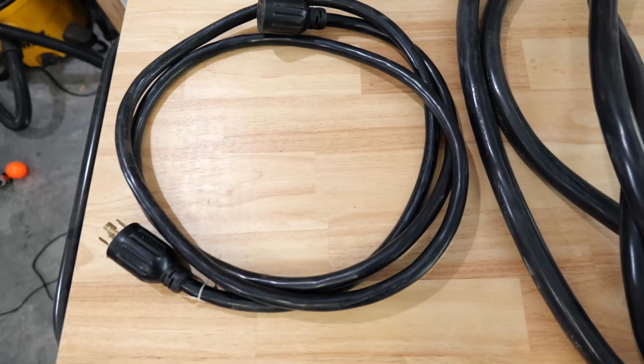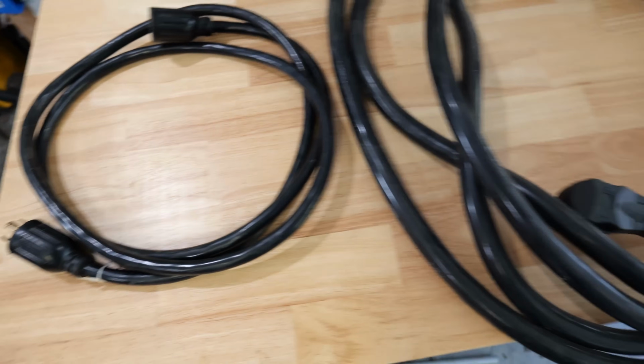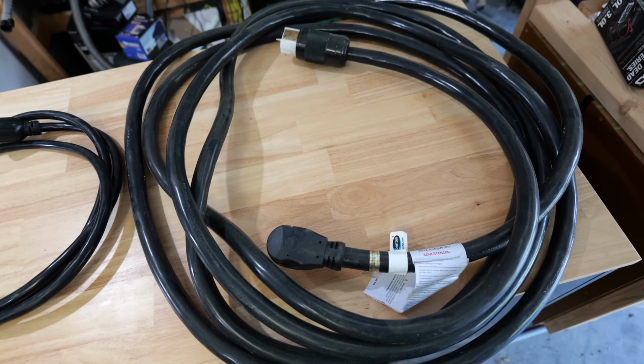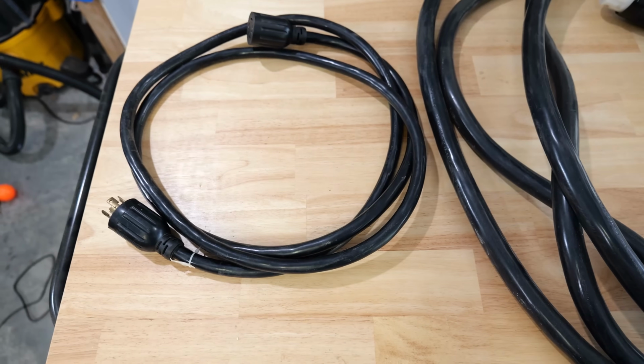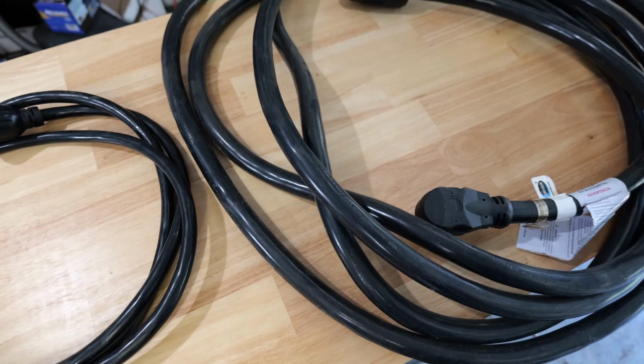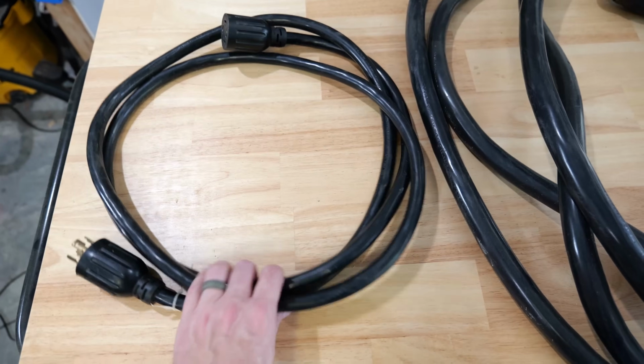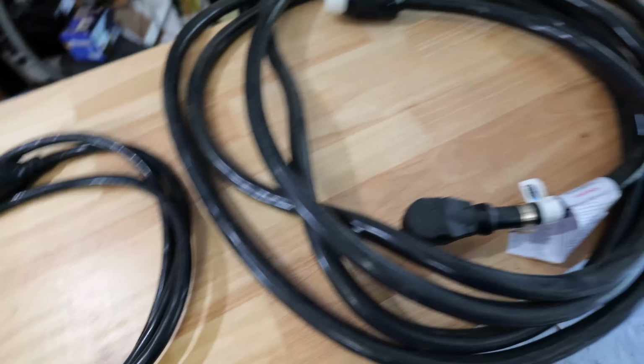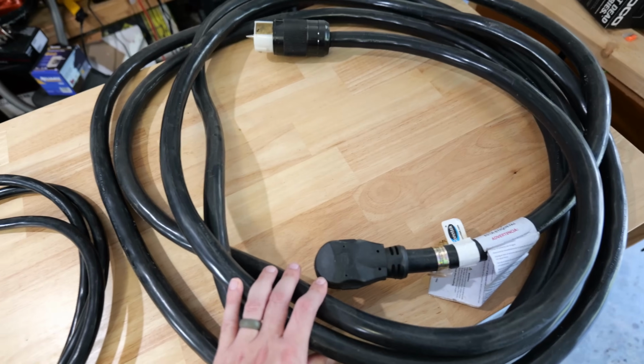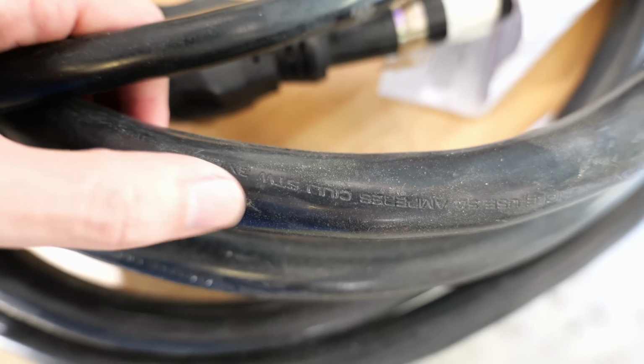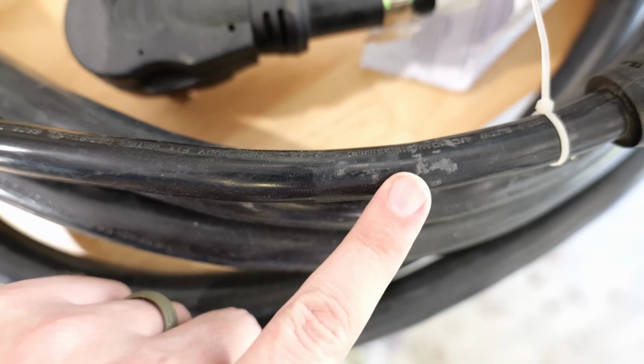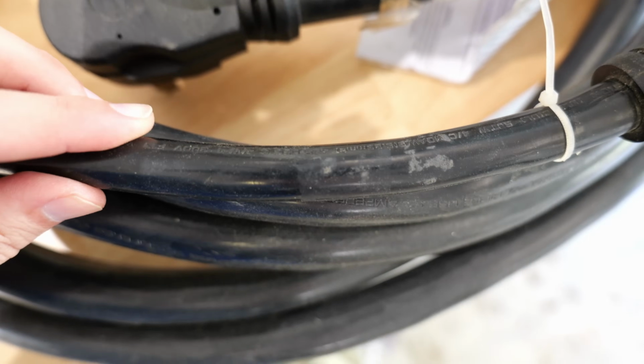All right, so now let's look at the generator cords. And I don't think it takes a genius to figure out which one of these is the 30 amp and the 50 amp. So yes, of course, this smaller one is the 30 amp and this bigger one is the 50 amp. So the 50 amp cord is all number 6 wires running through it. It's jacketed, so it has protection from the elements. The 30 amp cord is all number 10 wires running throughout it.